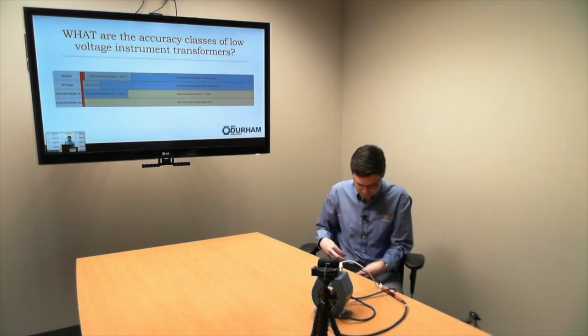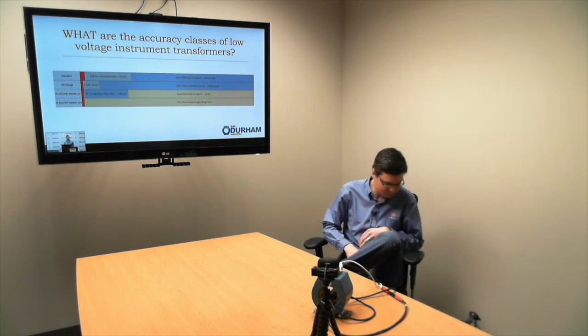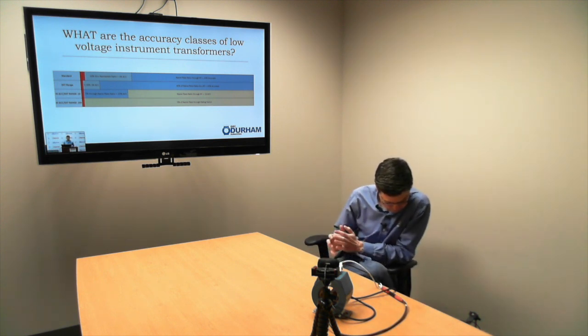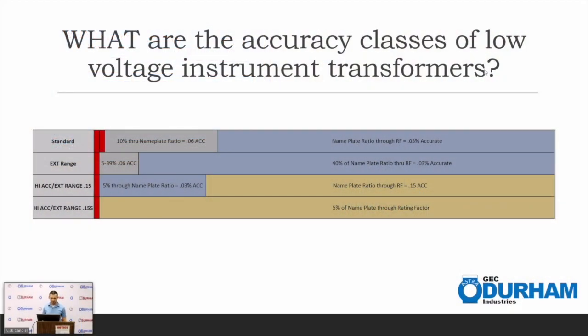Awesome. Thanks, guys, and my apologies for the technical glitch there. Had some issues transitioning back and forth between full screen and my presentation. So I'll do my best not to bore you, but with that said, thanks for the attaboys on the accuracy. And just to be clear, the ANSI guidelines for high accuracy transformers require that manufacturers provide a test report at 5%. So anything below that is, you could say, for free. So anyway, let's move on through our presentation.